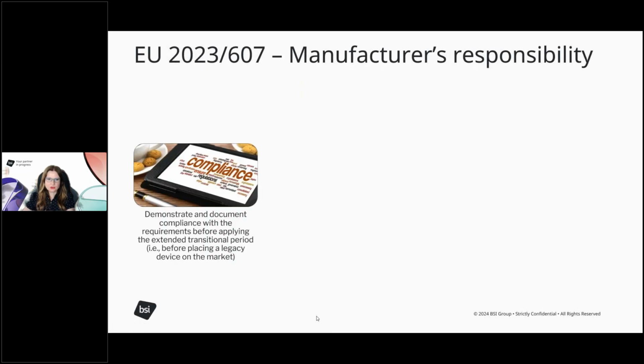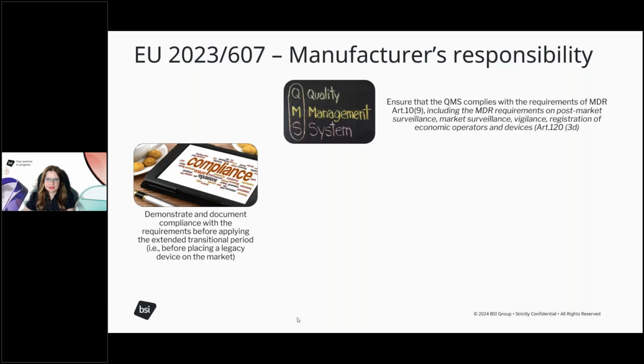So we saw what the conditions to be met are. So what are the manufacturer's responsibilities? The manufacturers shall be able to demonstrate and document compliance with those requirements and conditions that we saw before they place a legacy device on the market, so before applying the extended transitional period. The manufacturer needs to ensure that the QMS complies and is continuously in compliance with the requirements of the MDR as per Article 10.9, and this also includes those MDR requirements related to post-market surveillance, vigilance, or registration of economic operators and devices as per Article 120(3d).